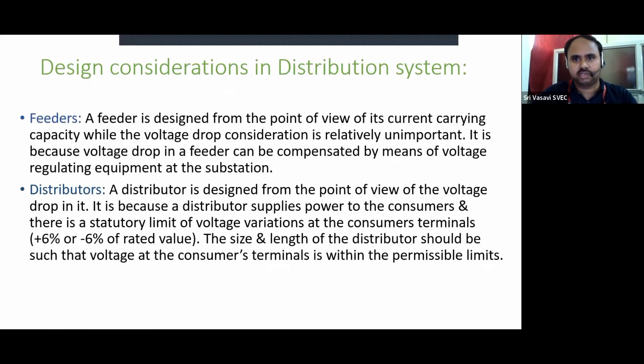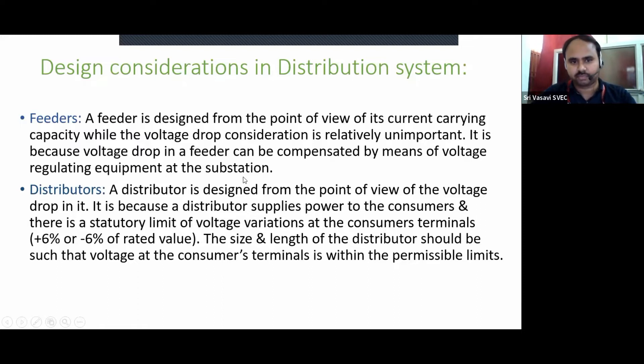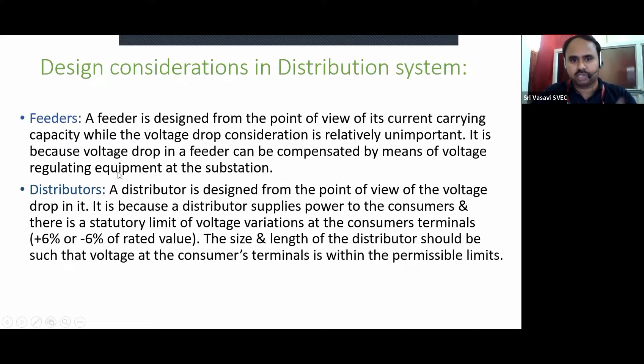Design considerations in distribution system: there are feeders and distributors. A feeder is designed from the point of view of its current carrying capacity, while the voltage drop consideration is relatively unimportant. This is because voltage drop in a feeder can be compensated by means of voltage regulating equipment at the substation. Therefore, we consider only current carrying capacity in feeder design, and voltage drop is relatively unimportant.